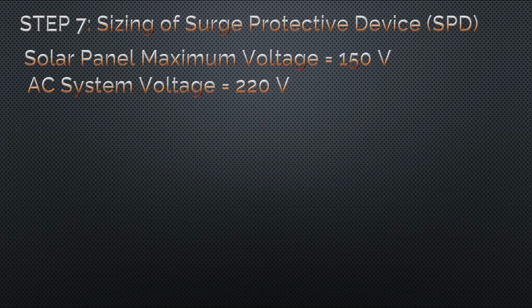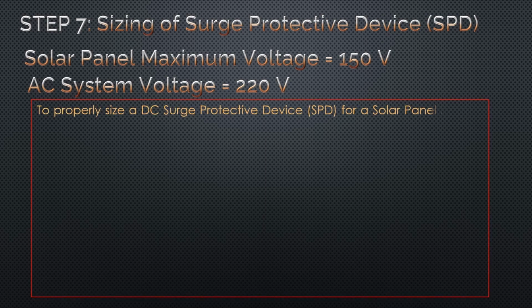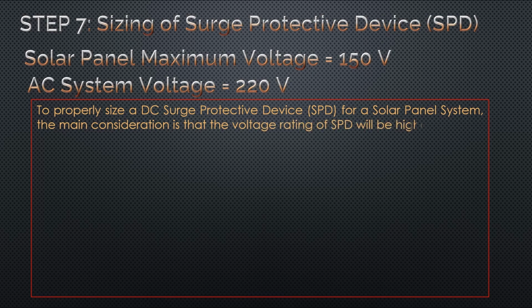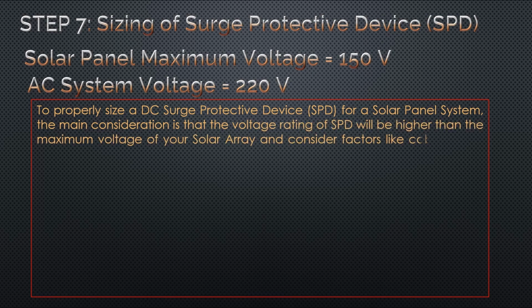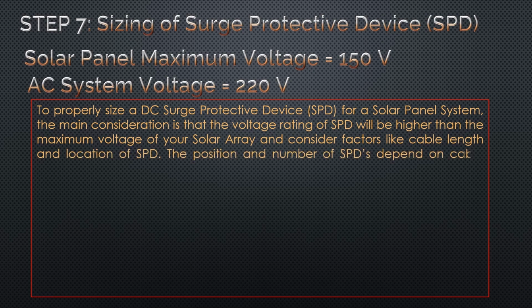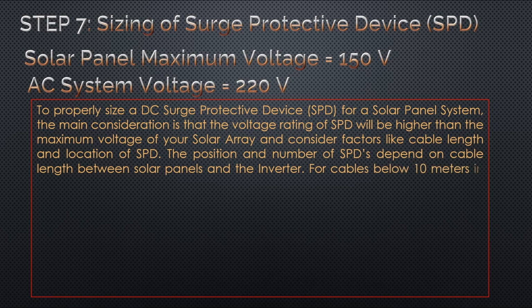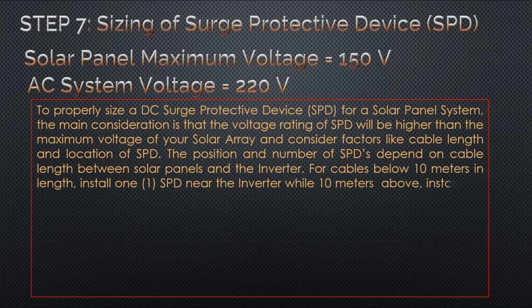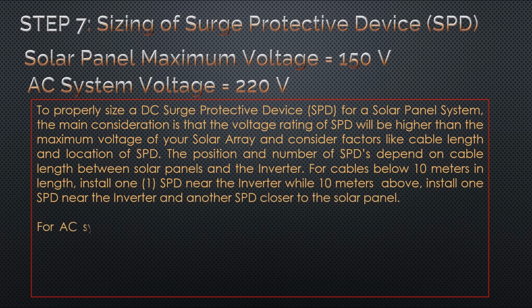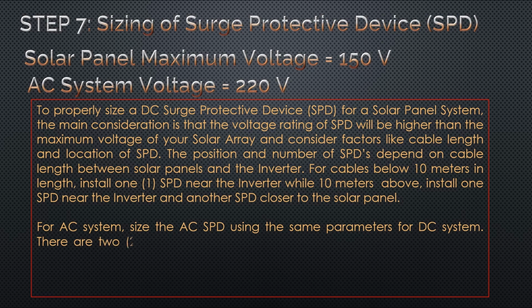Now we are in our last step, which is the sizing of the surge protective device. We already know from the nameplate of the solar panel that the maximum voltage is 150 volts DC. Also, the AC system voltage is 220 volts. To properly size a DC surge protective device for a solar panel system, the main consideration is that the voltage rating of the SPD will be higher than the maximum voltage of your solar array, and consider factors like cable length and location of the SPD.